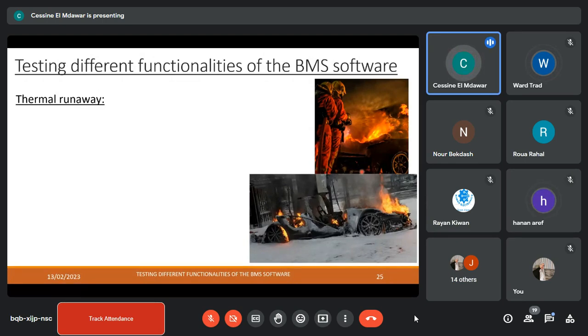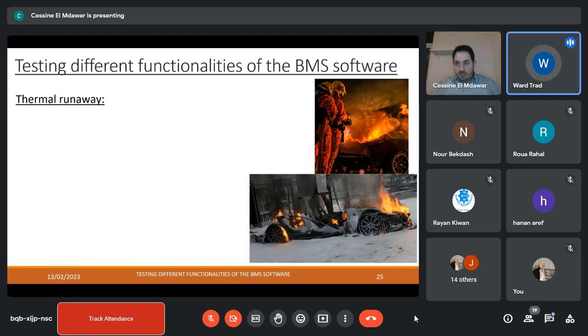Moving on. One scary scenario is thermal runaway, and this is also something that is designed within the BMS software, and I also do tests in hardware in the loop for the OEMs. So how do you think we start detecting thermal runaway in the battery? Thermal runaway is basically when the battery catches fire. So how should we detect thermal runaway using the BMS software? Any ideas? Is it a sensor that will detect the temperature, then at a specific temperature it will turn off the system?